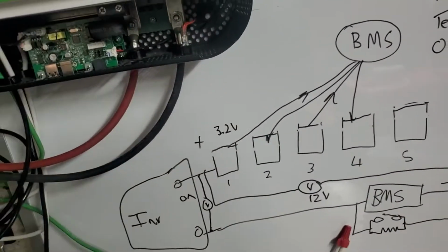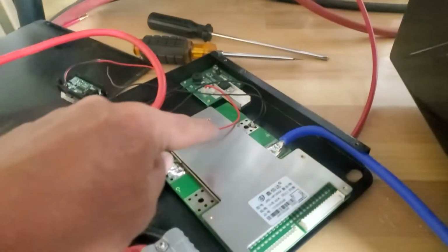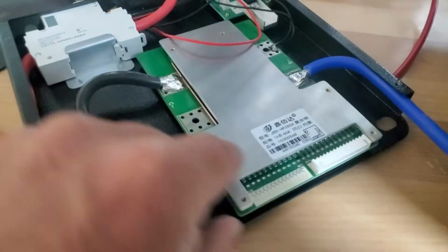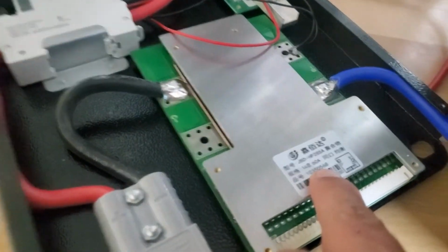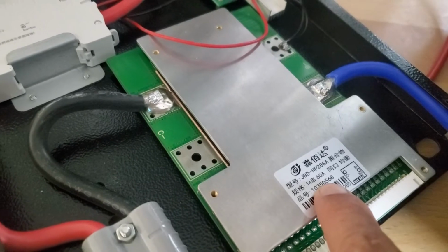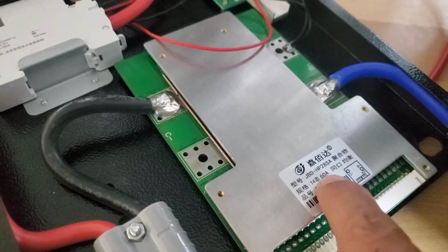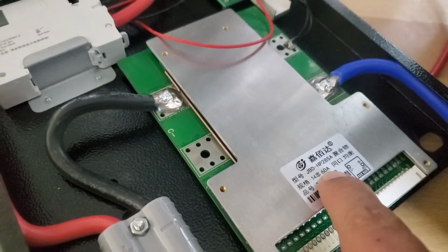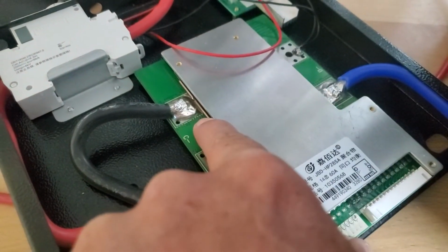Okay, so you can see the BMS over here is rated at a certain amperage. This one is rated at 60 amps. So in other words, if my inverter load is more than 60 amps, this thing's going to trip - it's going to go open circuit.